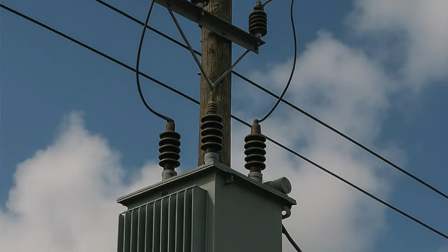I think in a lot of cases you need to specify what it's being used for, because the unit can be connected to a nice smooth linear load, which is unusual, or a very high reactive load. Reactive is motors, anything with coils is reactive. Nowadays lighting tends to be corrected, so electronics is quite linear. But if you're putting it onto massive machines or transformers, which is very reactive, that causes the power factor to shift.